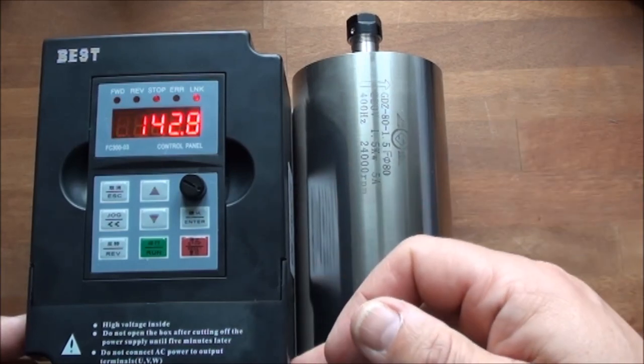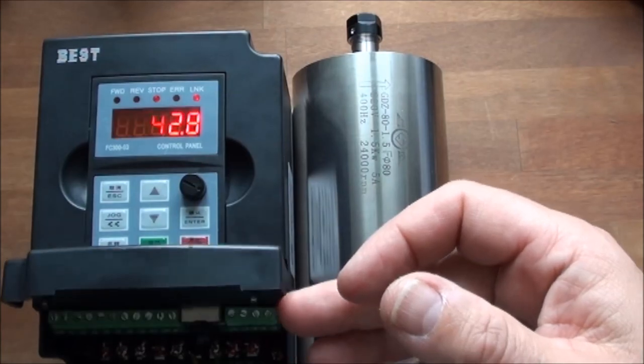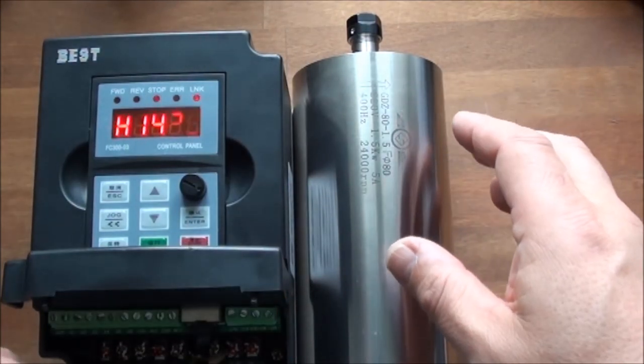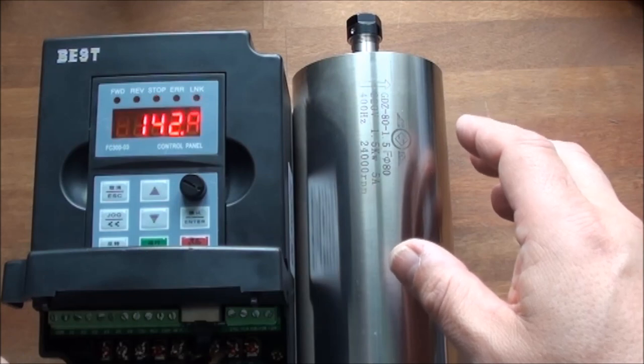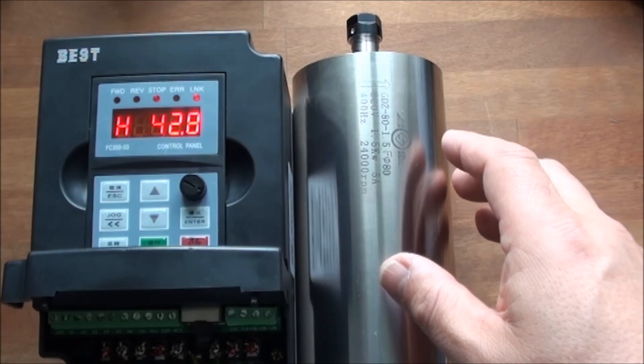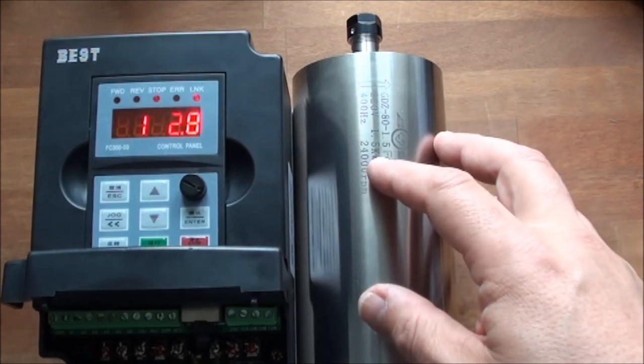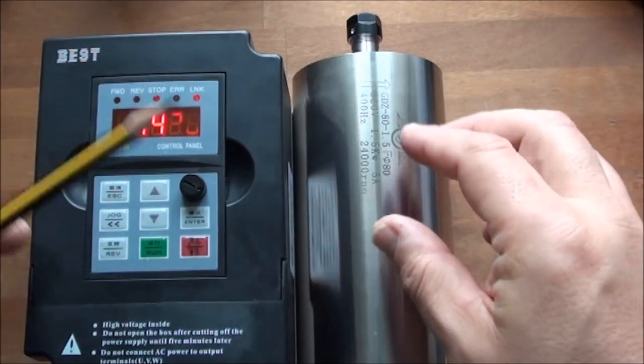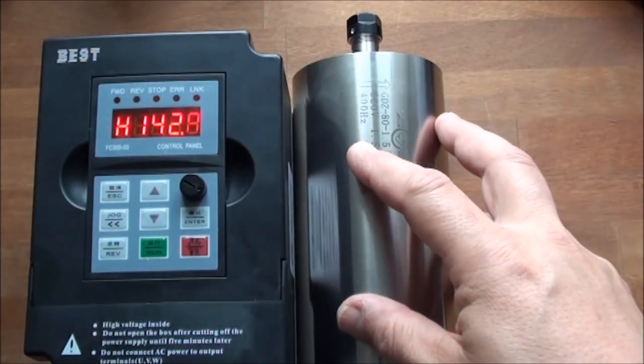By the way, if you have a bigger motor, have a heavy load, you may want to add a braking resistor here. And typically it's 100 or 200 ohms, 100 watt or so you add here. So it's a pretty big resistor that will burn off some of the energy and make it slow down quicker.